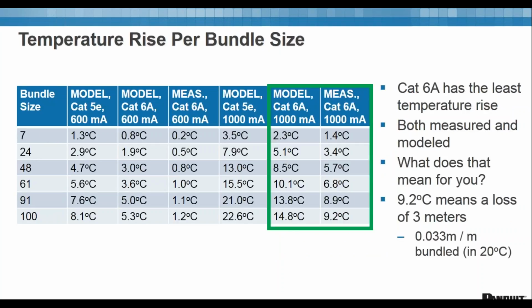Now what I've done is I've taken the temperature rise per bundle size. I'm going to draw two different things together: what the model says and what Panduit measured, and then pull this in with the table before to help you understand what's going on. For different bundle sizes on the left, you see that the cables get hotter. Comparing a 5E to a 6A system, Category 5E is getting significantly hotter. And comparing 600 milliamps to 1,000, the 1,000 milliamps does seem to have a significant rise, particularly on the 5E.